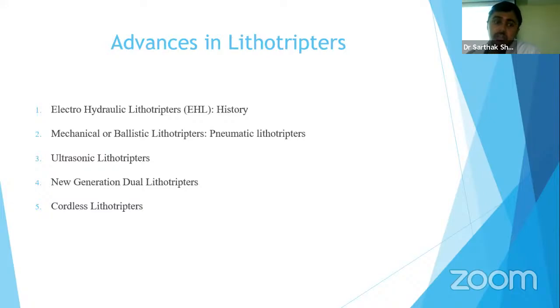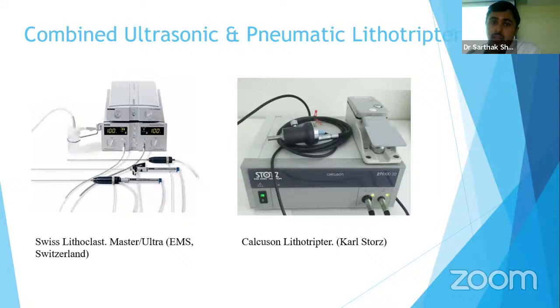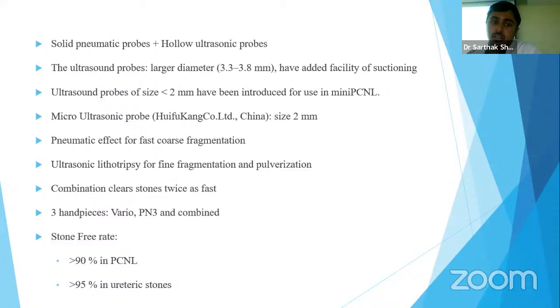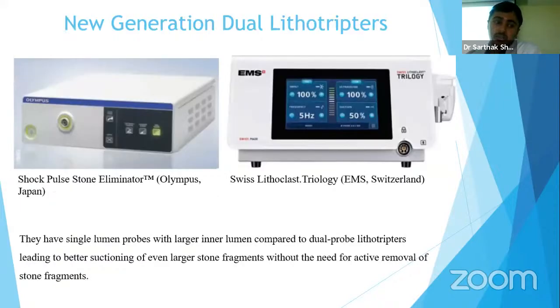Coming to advances in lithotripters, major advances have been in combined ultrasonic and pneumatic lithotripters. These were the slightly older ones, the Swiss LithoClast Master Ultra and the Calcuson lithotripter. They consist of a solid pneumatic probe plus a hollow ultrasonic probe. The pneumatic effect is used for fast coarse fragmentation, while the ultrasonic is used for fine fragmentation and pulverization. And a combination of these gives clearance of stone twice as fast. The stone-free rates are more than 90% in PCNL and more than 95% in ureteric stones. These are the new generation dual lithotripters, mainly the shock pulse stone eliminator and Swiss LithoClast. They have single lumen probes and a larger inner lumen, which means even larger stones can be sucked out.